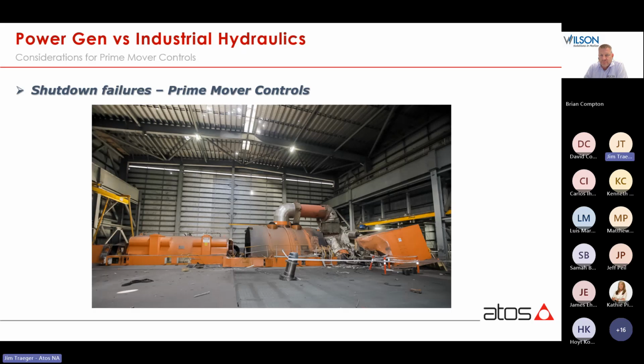Pretty bad situation. So, basically, in summary, when it comes to power generation, the most critical controls are going to be for the prime mover. They may be slightly different than the circuits we use in industrial hydraulics, but generally in respect to the fail-safe conditions, the proportional valves, and the additional redundant circuits required. You need to respect the power the prime movers can unleash and follow the industry's best practices to avoid serious injuries.